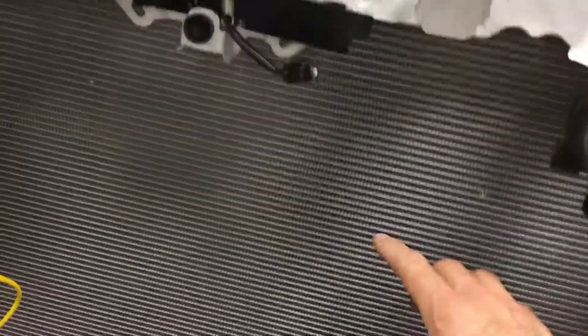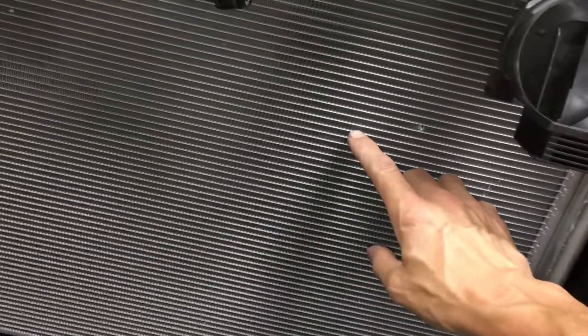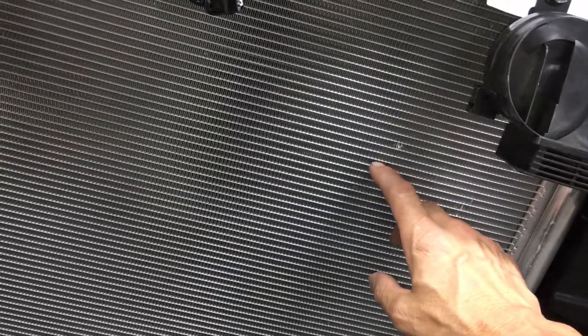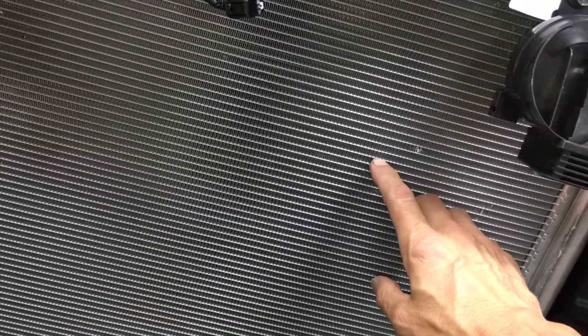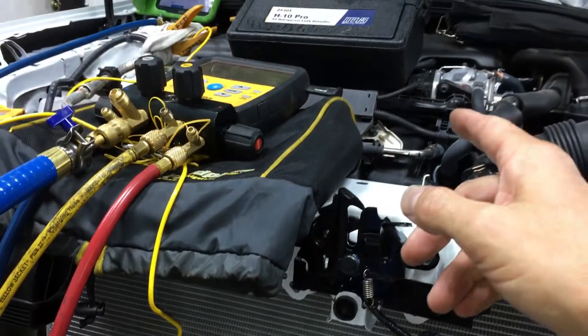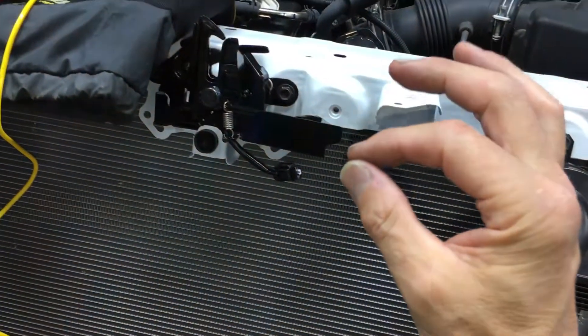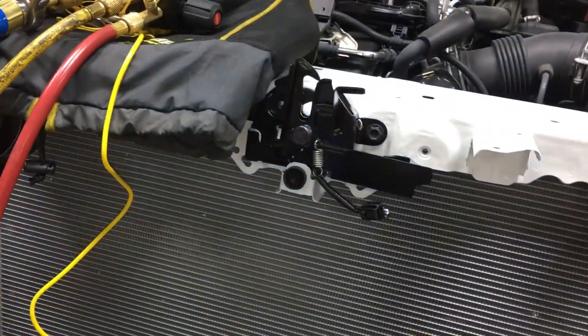Your tubes are just a little bit thicker than Reynolds Wrap aluminum foil — the heavy-duty commercial aluminum foil they use in restaurants. This is barely thicker than that; that's how thin these walls are. Same with your evaporator. And so you start attacking this with even a weak acid solution. Over a period of time it starts eating away and you get those little micro pinholes.